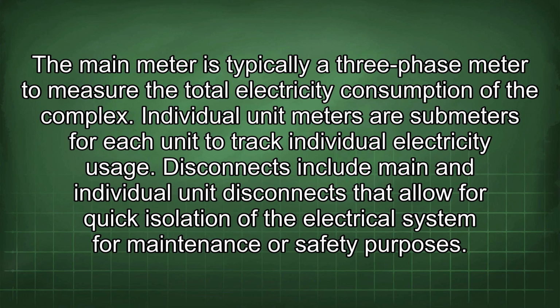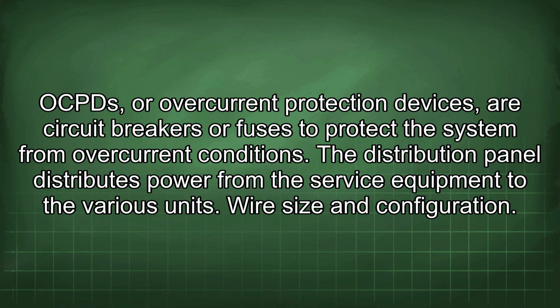Disconnects include main and individual unit disconnects that allow for quick isolation of the electrical system for maintenance or safety purposes. OCPDs, or overcurrent protection devices, are circuit breakers or fuses to protect the system from overcurrent conditions. The distribution panel distributes power from the service equipment to the various units.